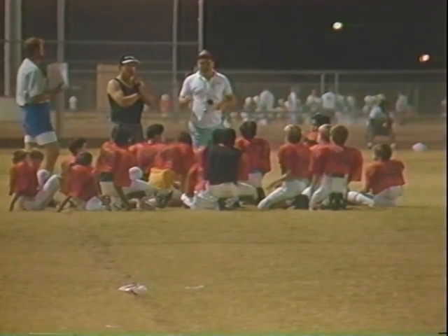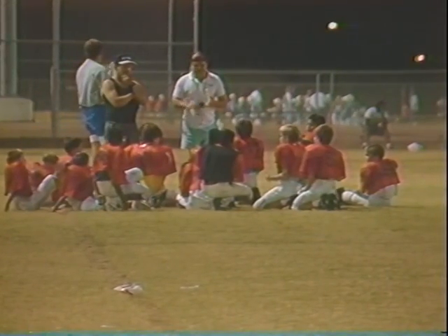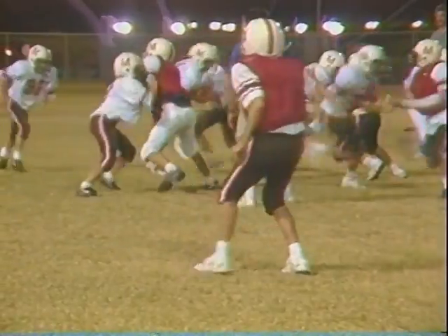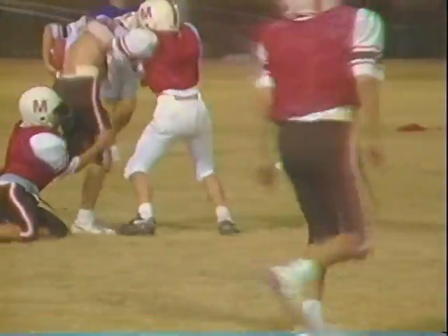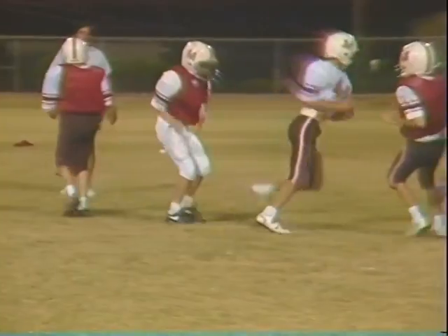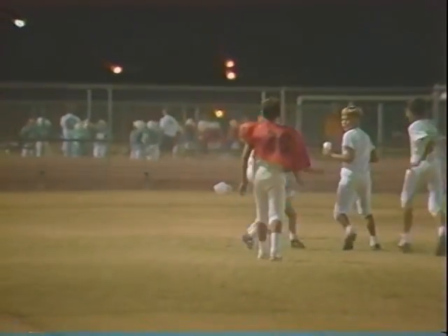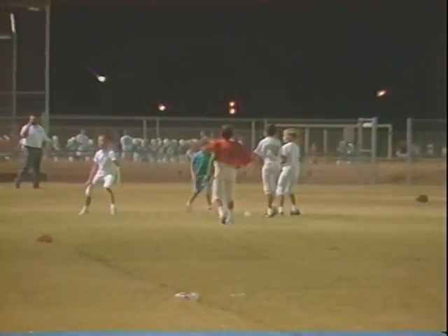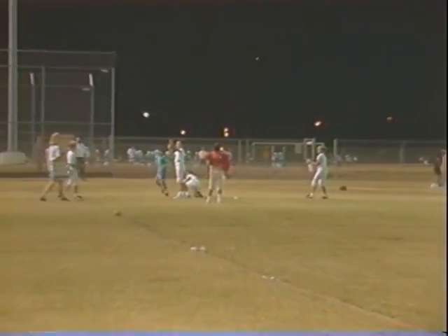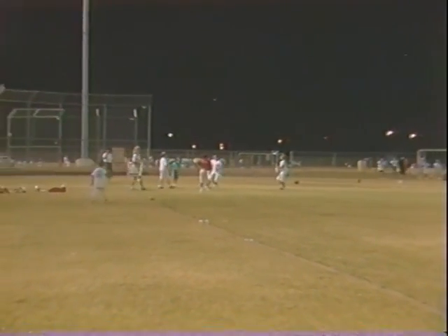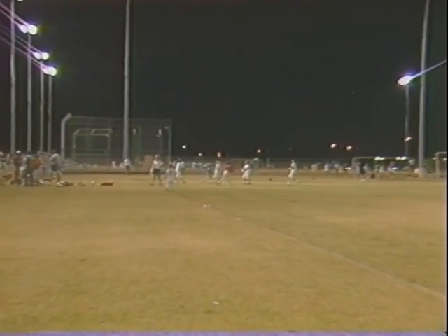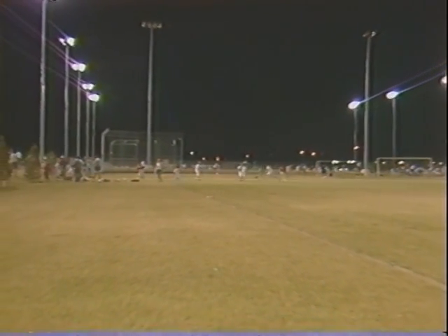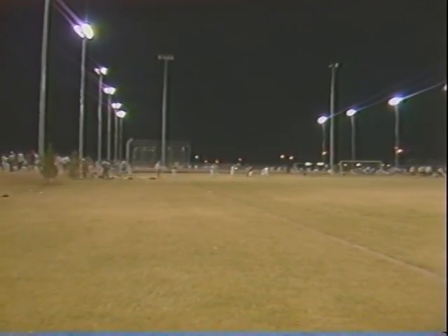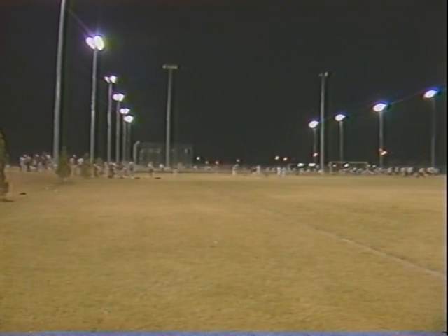We feel that that is giving us maybe half an hour to 15 minutes of advantage every day in that the lights are not burning unnecessarily. The 344 kilowatts of energy that are used to light these 6 fields represent a cost of $28 an hour to operate. So if you can shave off 15, 30 minutes of operating time every day, that does stack up. Astro-digital timers are also being used at Tempe's other parks.